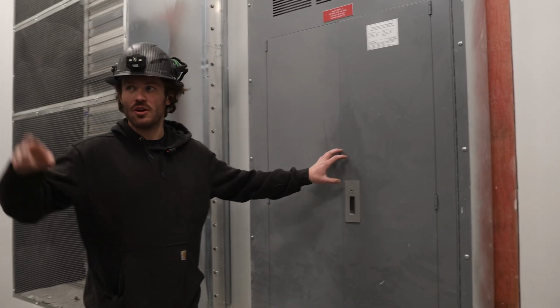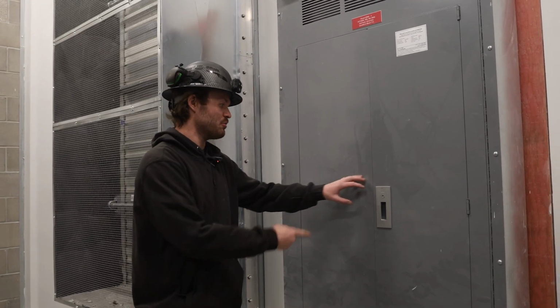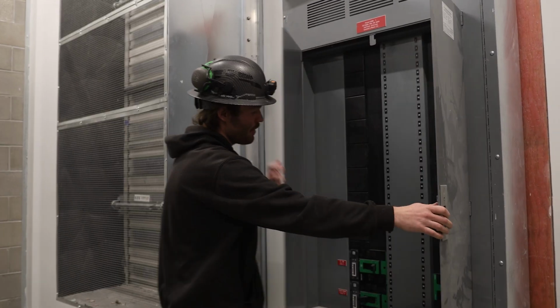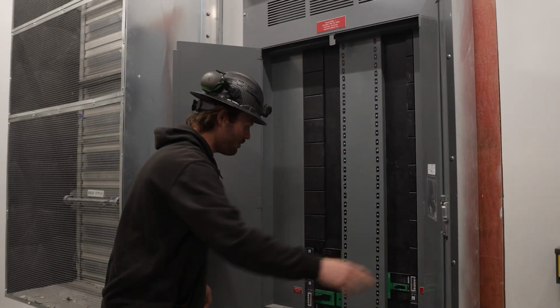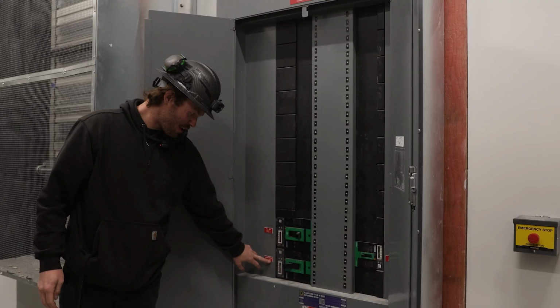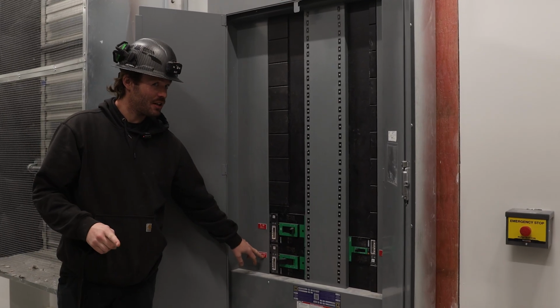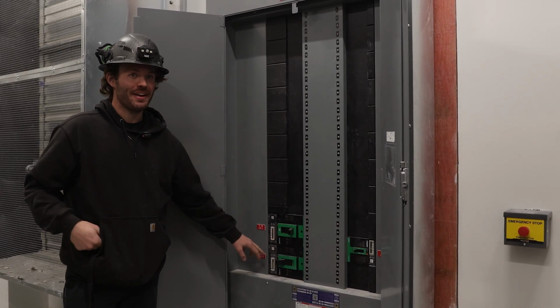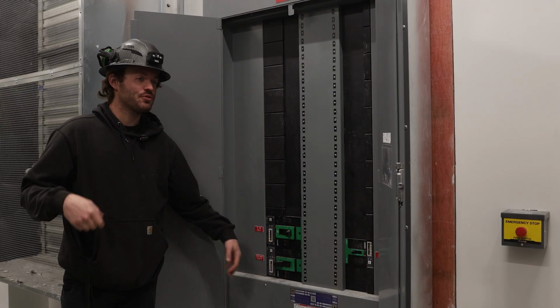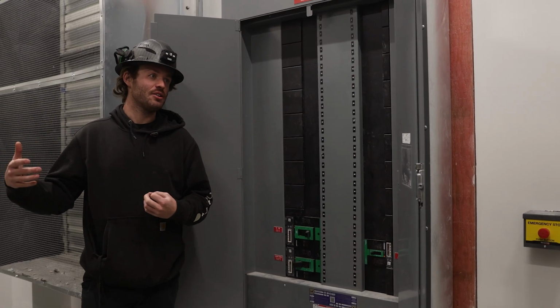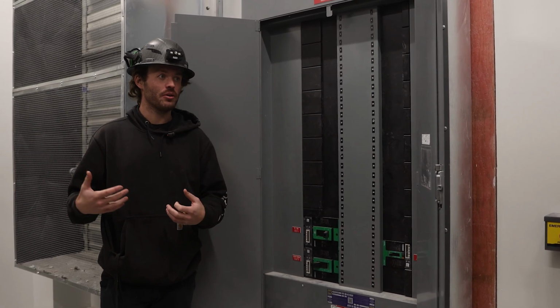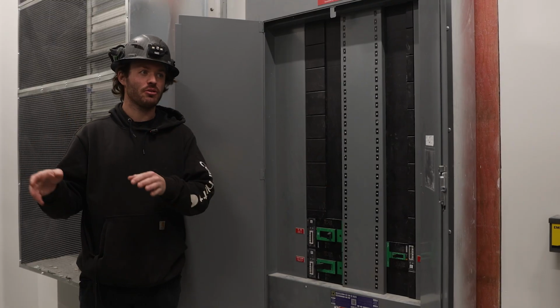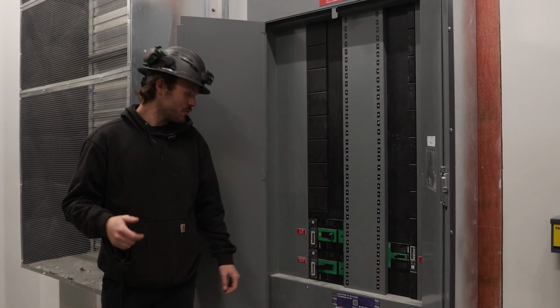This is our emergency power distribution. So from the breaker on the generator, comes into this guy, and then we got 3 feeds. One being to our load bank panel, which is installed. Load bank panel is for remote tie-ins for when we do our annual load testing of it. The 2-hour load test, we bring a big toaster, hook up our own cables, run it for 2 hours.